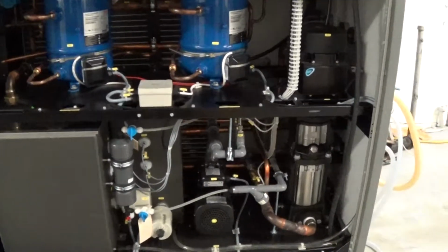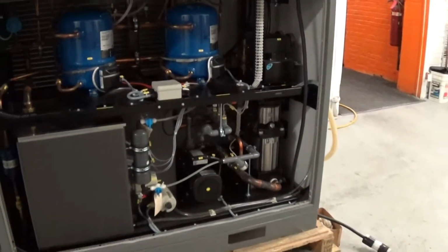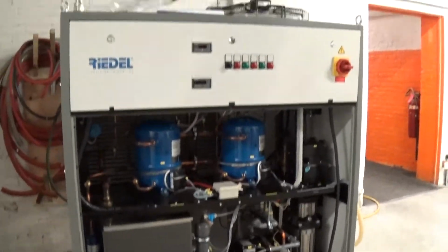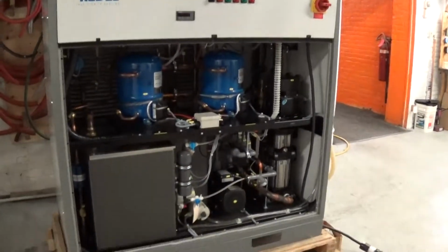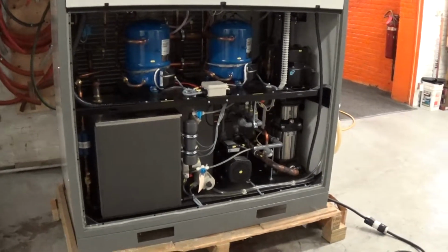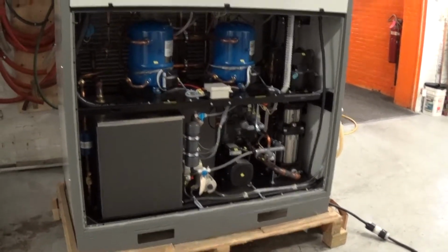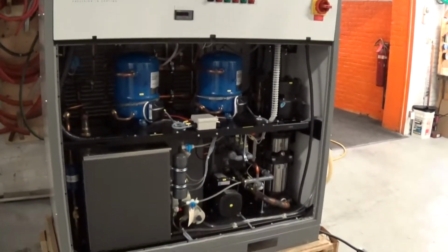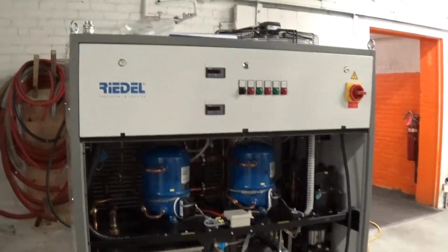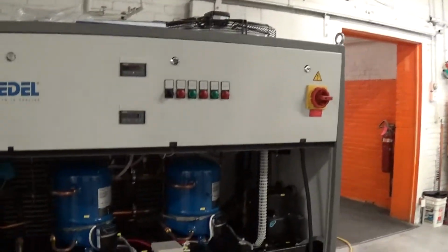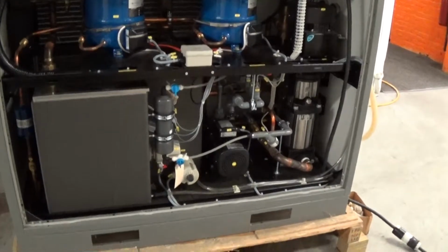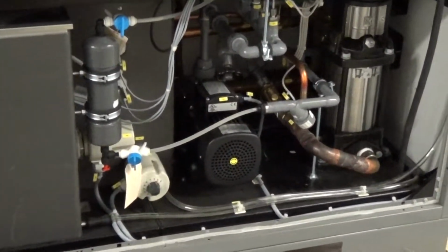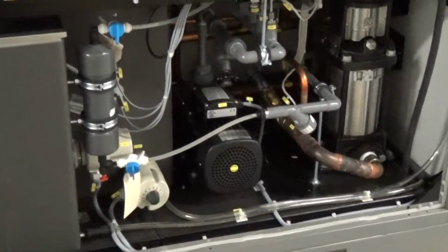Now for this application, this is going to a customer in plastics manufacturing out in Texas, I believe, or similar to that. And we've done this many times. We do not need to use that secondary circuit. So internally in the control cabinet up here, we just disconnect the second pump and we ship it with all the ancillary stuff for that secondary circuit. But that pump's not going to be running.